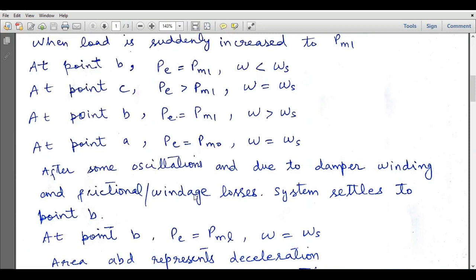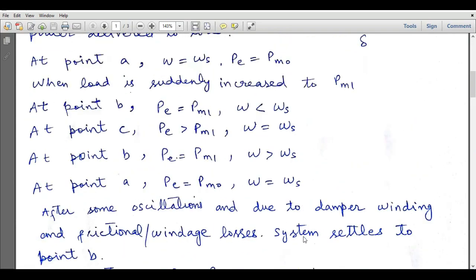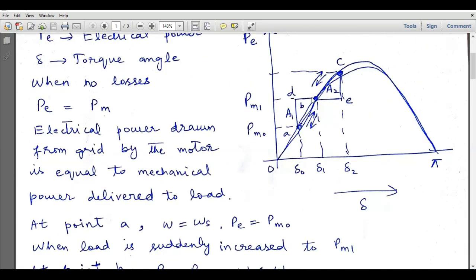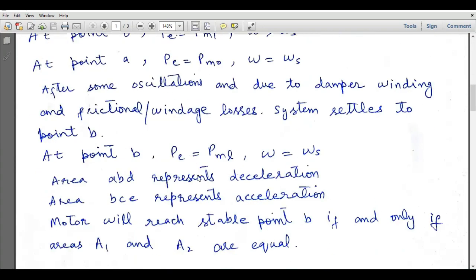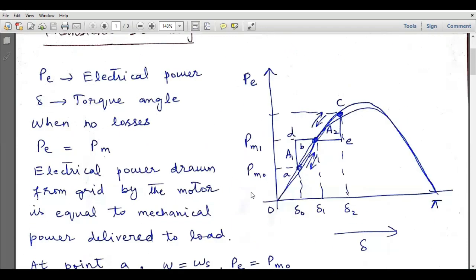After oscillations, due to damper winding and frictional or windage losses, the system settles to point B. At steady state at point B, pe equals pm1 and omega equals omega_s. We can observe two triangles: triangle ABD corresponding to area A1 and triangle BCE corresponding to area A2. The motor will reach stable point B if and only if areas A1 and A2 are equal. This condition is called the equal area criteria.